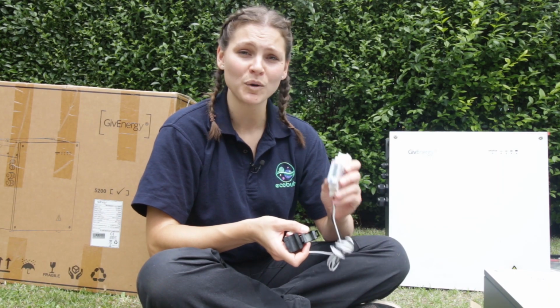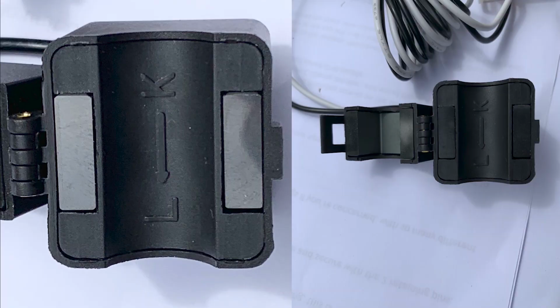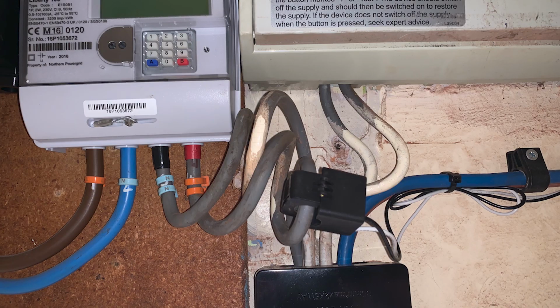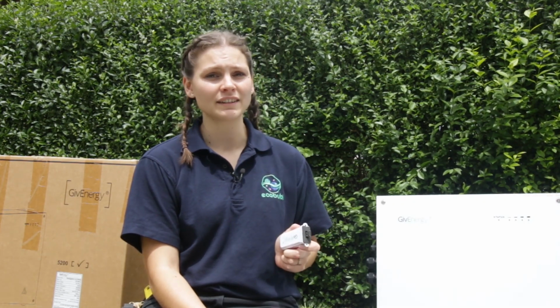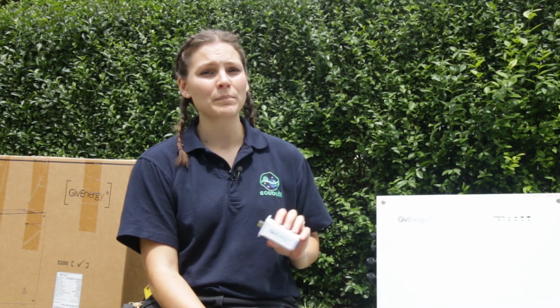So this is the EM115 grid monitoring meter, and it has its own CT clamp at the bottom. Make sure the arrow in the middle of this is facing towards a consumer unit and it's secured properly. This is your GivEnergy dongle. This is connected to the bottom of your inverter. You can also get this in a 3G version, and GivEnergy provides you with a data card for that. This allows you to get access to all your web-based programs so you can see how your system is performing.